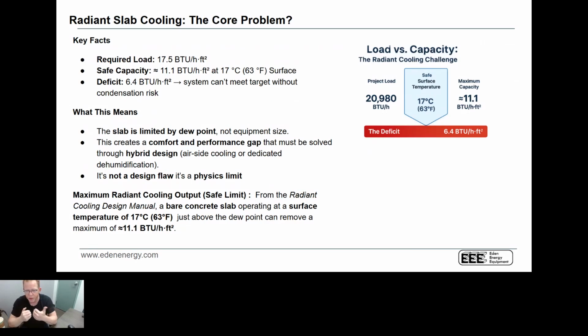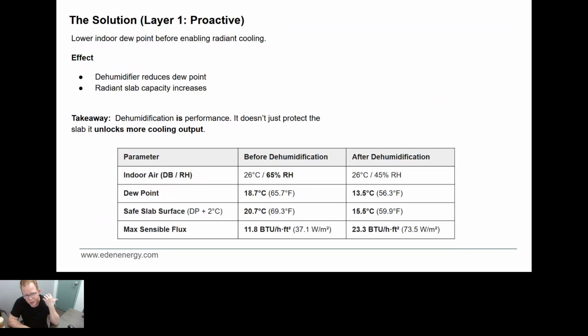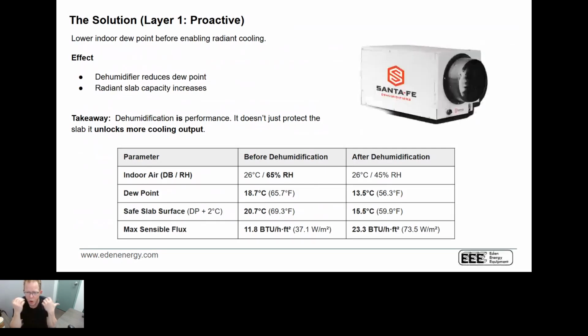The challenge is it's the unintended consequences. If you've never done it before, you definitely don't want to wing a radiant cooling floor. You don't want to wing anything, but there's a lot of radiant heating systems that John Siegenthaler has coined the phrase that they're running but not working properly. You do that with a cooling system, you're going to run into trouble. So the easy way to get around that and the proactive effect is you need to use a dehumidifier. And obviously you want to work with a designer and an engineer just to make sure you're doing the system properly.